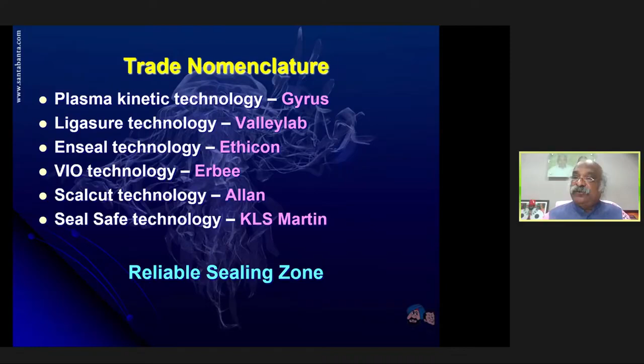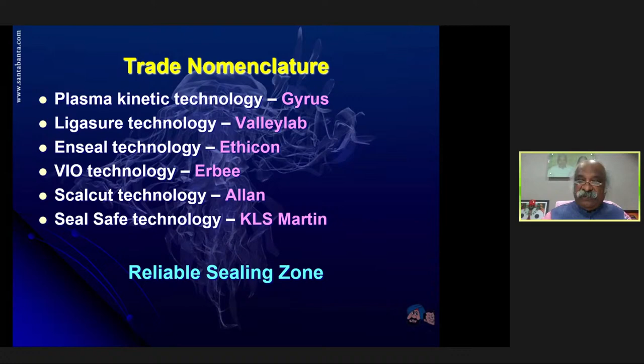And therefore I have told that it is low voltage, high power and compressive force which is responsible for the vessel sealing. It is also accompanied by tissue impedance feedback, so that auto-regulation or modulation cannot happen without tissue impedance feedback. So all the new generation electrosurgical generators have tissue impedance feedback. So ladies and gentlemen, all gynecologists, this is a very important instrument, don't compromise, quality is a major thing. And although this is a combination of instruments, the cost-effective part is also there.